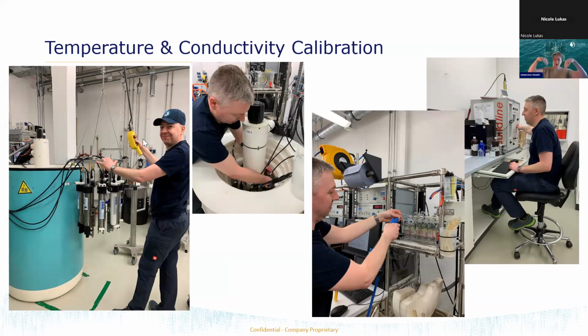And we will load multiple instruments into each bath. The bath has a temperature and a conductivity reference that's inside of it. And we typically run the baths overnight. So they step through a number of different points along the temperature and conductivity range that is typical in the ocean, and collect data overnight. And at each calibration point, we're doing the same thing. We're polling the reference and saying, what is the actual temperature today in this bath right now? What is the actual conductivity? And then we're comparing that to your instruments.